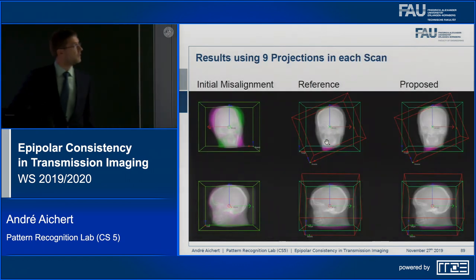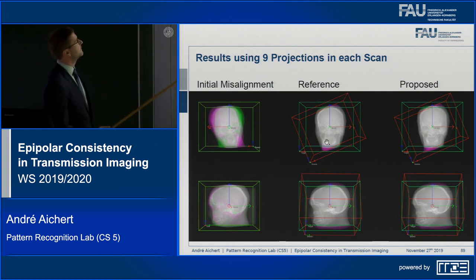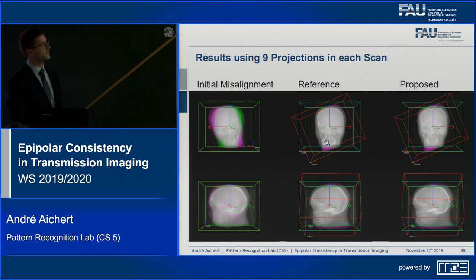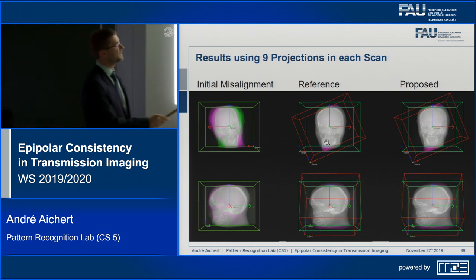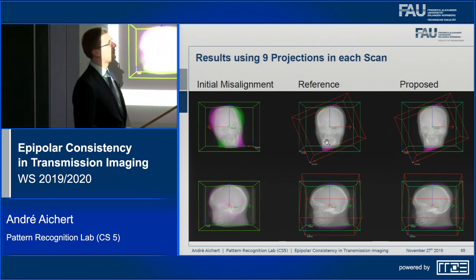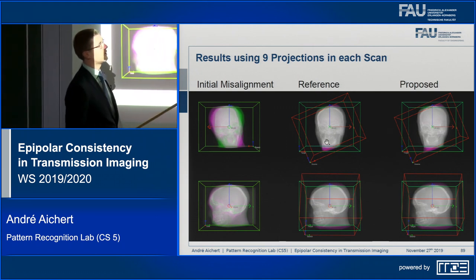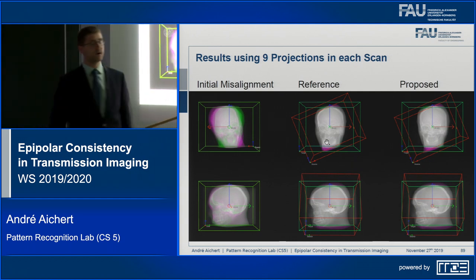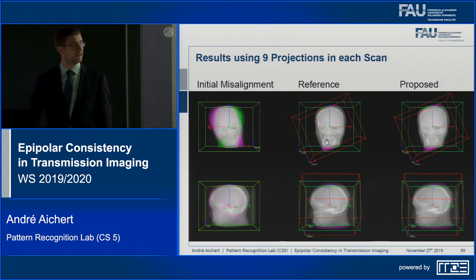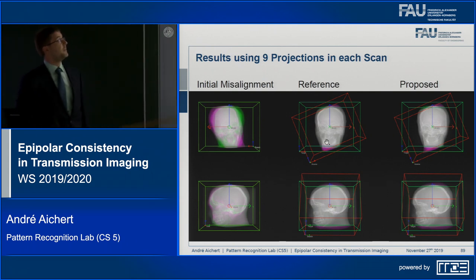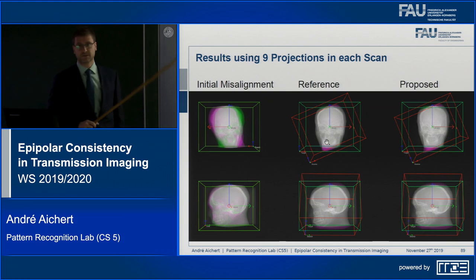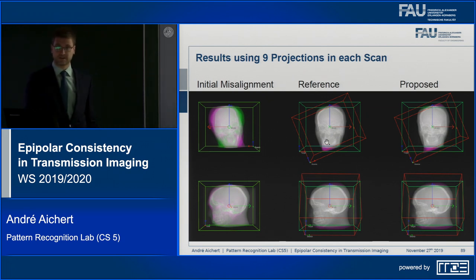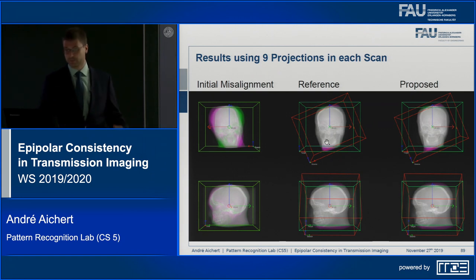The end result shows the reference, the initial misalignment — lots of green and purple because the two images don't match — and the proposed result, which closely matches the reference. Where the images are gray there is no color difference, indicating correct alignment. Remarkably, we used only nine projections out of several hundred and still achieve the same result as intensity-based registration that also performed a full reconstruction.